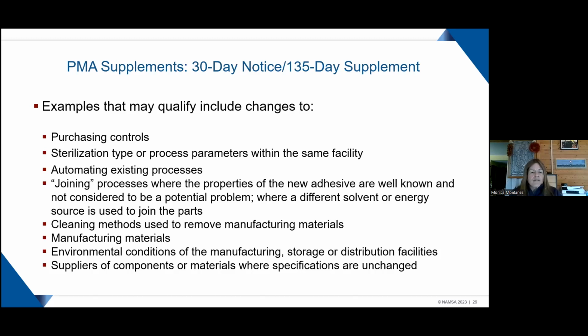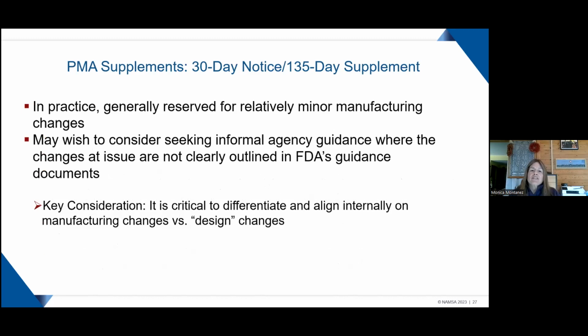Changes in your supplier of components or materials, where, of course, your specifications do not change. And in practice, it's generally reserved for relatively minor manufacturing changes. You may want to consider, of course, reaching out to the agency to talk about any changes that are not clearly outlined in FDA's guidance document, because believe me, not everything is in those guidance documents. So, of course, the key consideration here is to ensure internally that it's critical to differentiate and align internally on the manufacturing changes versus design changes.